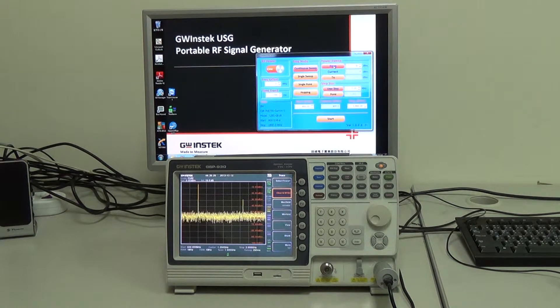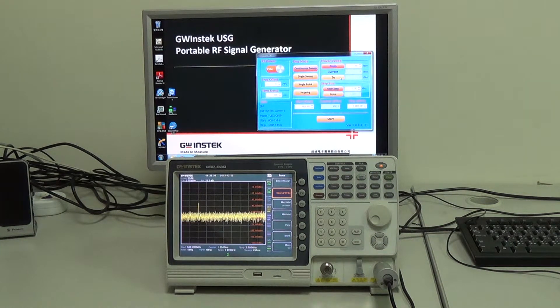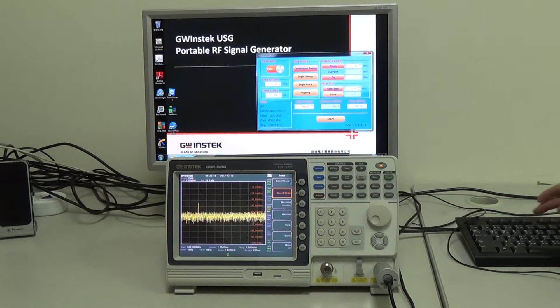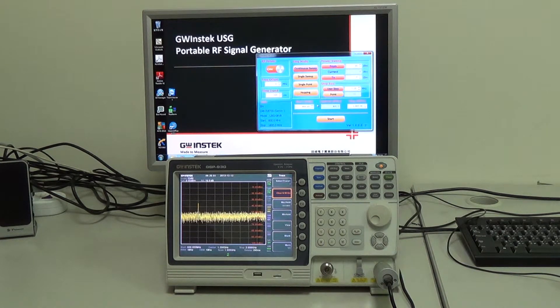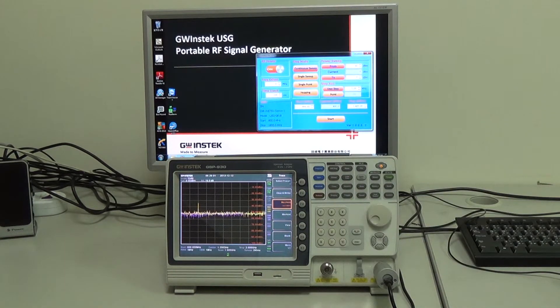Next, we're going to enter a power sweep from minus 30 dBm to 0 dBm. Enter user step 5 MHz, 201 points, start frequency 800 MHz, stop frequency 1.8 GHz. Next, press F3 for maximum hold and click on start.